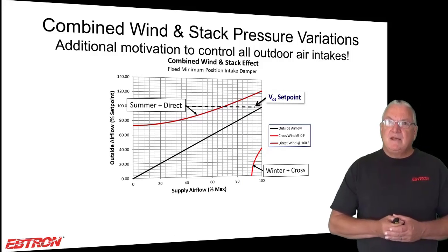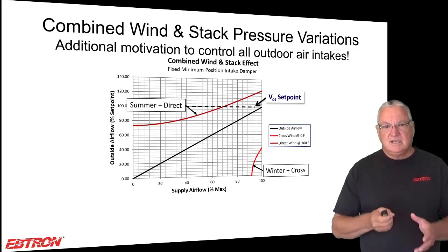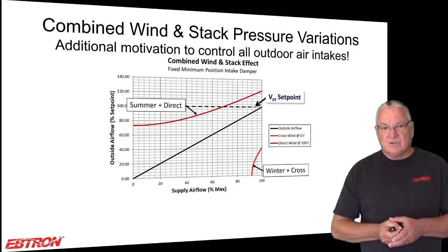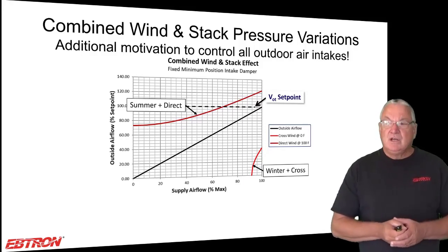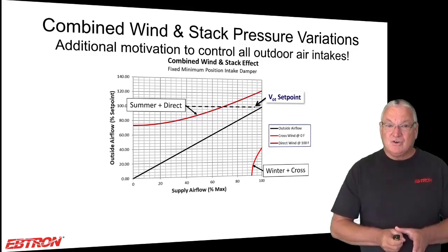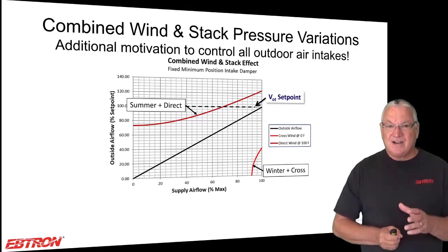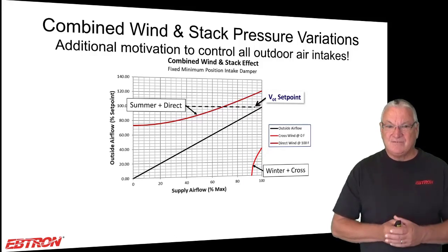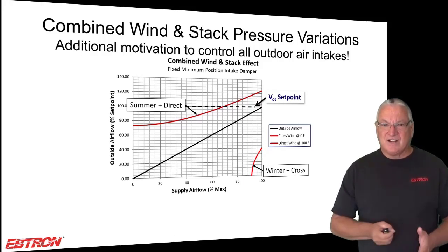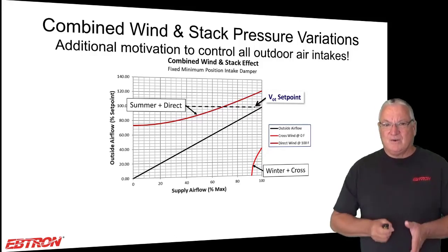It amazes me, all the things that I see people doing today. Oh, we're trying to reduce outdoor air and we're trying to do this. That's fine, but you still have to measure it and you still have to control it, because you can't have this kind of variation in intake flow rates going on. It's not this magic number that you set and forget. It doesn't work that way.